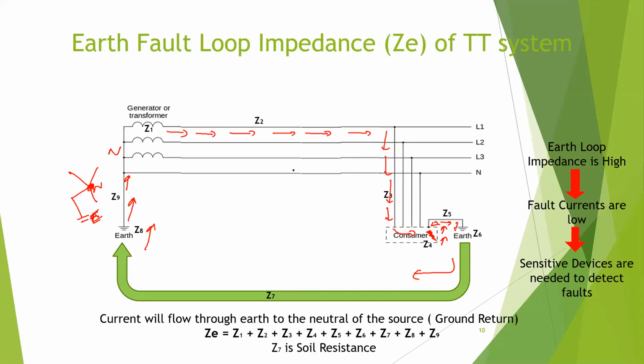If you observe the TT system, you can see the path that the current flows through is not completely metallic. You have earth here, and after that you have the path through soil. That path is not metallic, but starting from here, this is a copper or aluminum conductor, and the enclosure is also conductive. So this path is metallic and this path is not metallic. Due to that, in a TT system, our earth fault currents are a bit lower. Usually in an installation, we take this earth loop impedance as 10 ohms. We are going to see these things in the lab in this lecture series. Usually the earth loop impedance will be 10 ohms.